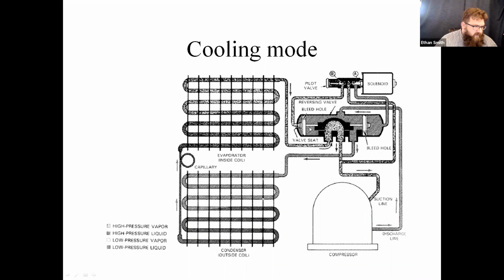Before we do that, Keith does bring up a good point about ratings. When we pull up the ratings on heat pumps, guys, it does specify your indoor coil in those ratings. Make sure you're using rated matches, guys. I will strongly recommend that you stay with the brand of the outdoor unit for the brand of indoor coil. Third-party coil ratings may or may not be totally accurate. We see trouble with that. So back to our reversing valve, guys.